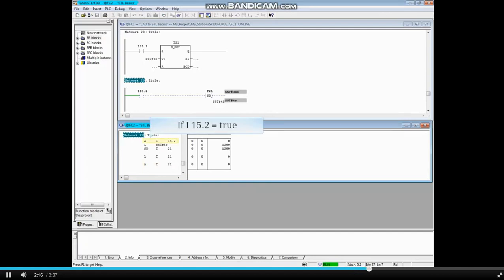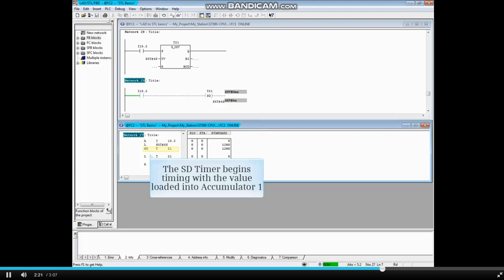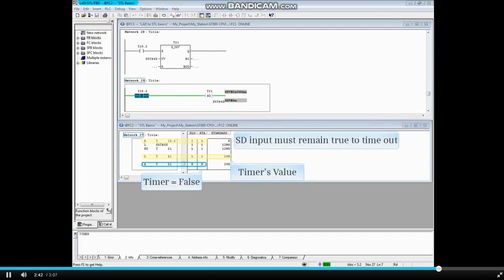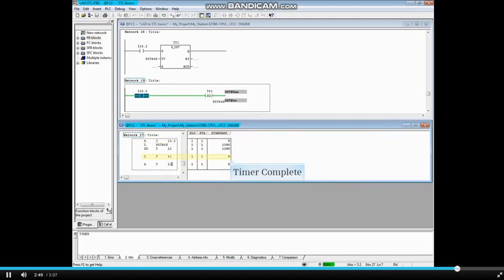When input 15.2 goes true, the SD or on delay timer will begin timing according to the time value in accumulator 1, which is 5 seconds. The input must remain true for the timer to time out. The coil is false while timing and goes true after the delay. The on delay timer is complete and the timer's coil is true.